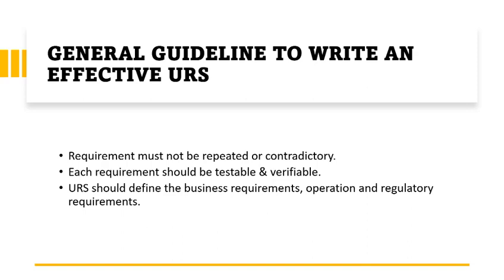It is very important to write a URS by taking input from the end user, whether it is your analyst or operator, and a peer review process should be followed to identify any errors. The URS should also define business requirements, operational requirements, and regulatory requirements such as security control, IT control, or 21 CFR related requirements.